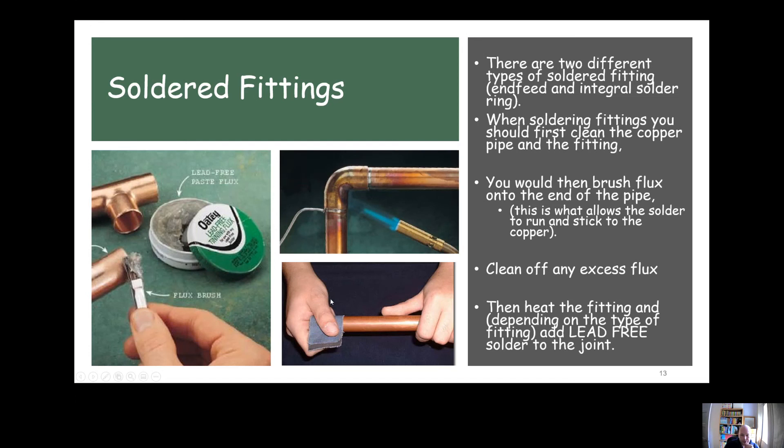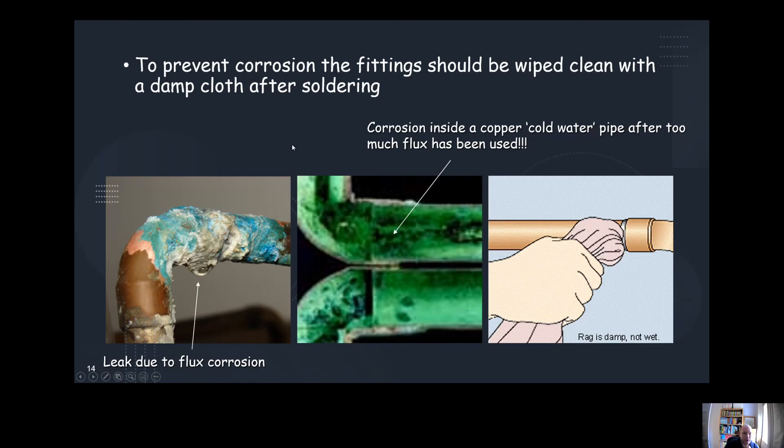Clean off any excess flux so it's not running down the pipe, and then heat the fitting up using a blowtorch. If it's an end feed fitting, you'd need to add solder to it like you can see in this picture here. If it's an integral solder ring fitting, you would just heat it until you see that band of solder drop out of the solder that's already been integrated into the fitting. After you've finished, make sure you give it a wipe to remove any excess flux. The flux is there essentially to stop the pipe from oxidizing during the process, which allows the solder to be pulled in and stick to the surface. But the flux is corrosive, so if you leave it on the pipe for a long period, it can cause corrosion.